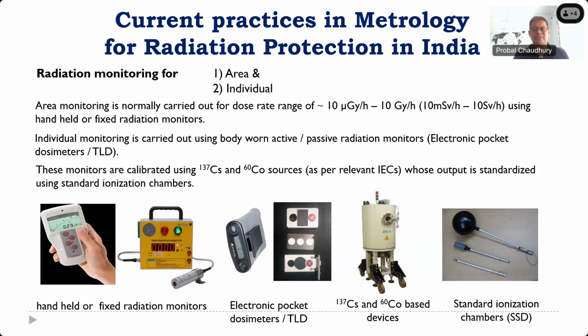Then, current practices in metrology for radiation protection in India. We have radiation monitors for, as I mentioned, area monitoring. That means for any radiation facility, you have to have area monitoring. The area has to be continuously monitored for any elevated level. And then there is individual monitoring, which measures how much dose is received by the persons working in the radiation environment. Area monitoring is normally carried out for different dose rates based on the applications. I have given a range of 10 microgray per hour to 10 gray per hour. This is the range where we are working.